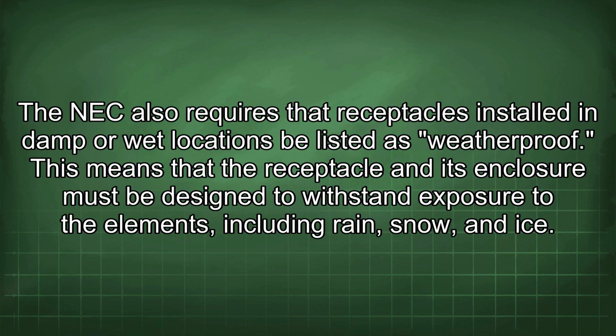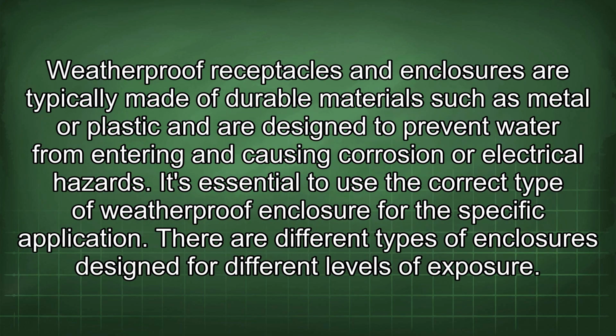The NEC also requires that receptacles installed in damp or wet locations be listed as weatherproof. This means that the receptacle and its enclosure must be designed to withstand exposure to the elements, including rain, snow, and ice. Weatherproof receptacles and enclosures are typically made of durable materials such as metal or plastic and are designed to prevent water from entering and causing corrosion or electrical hazards.